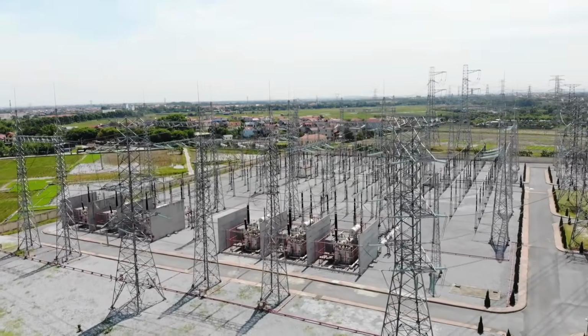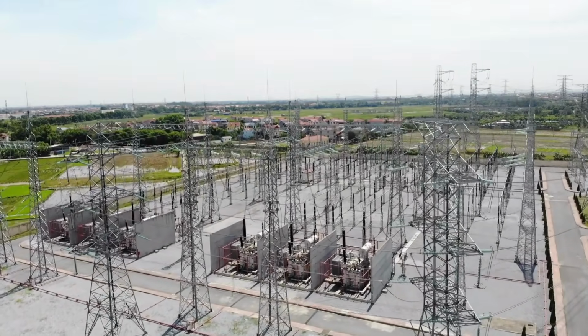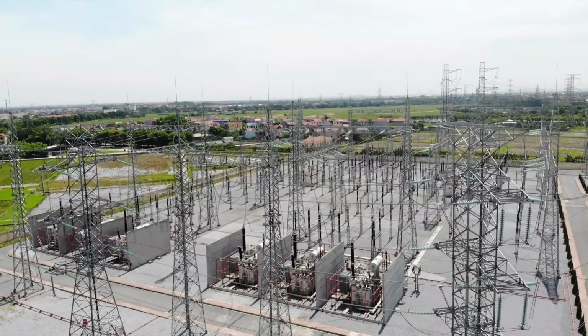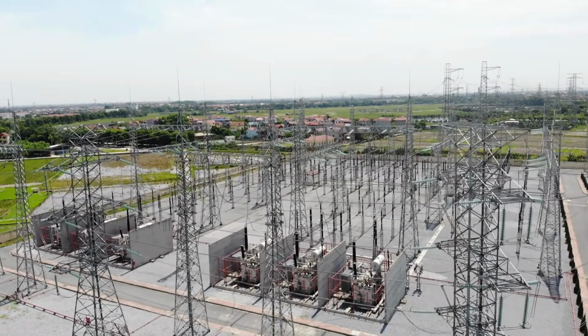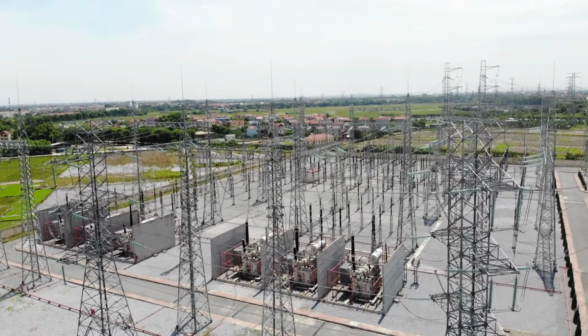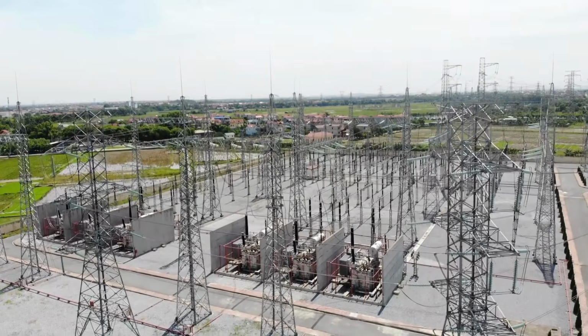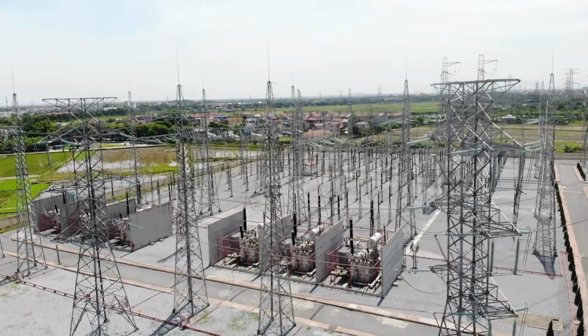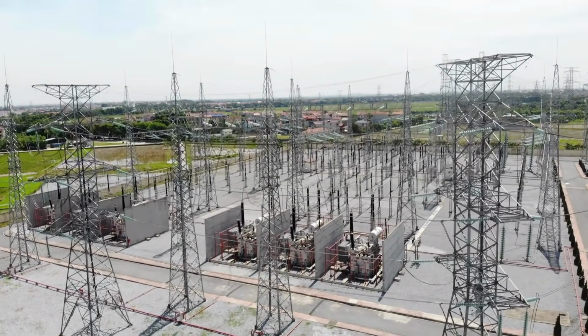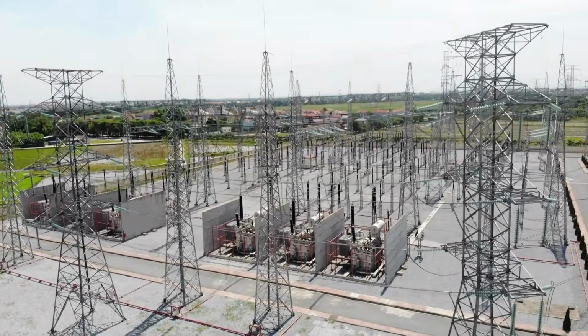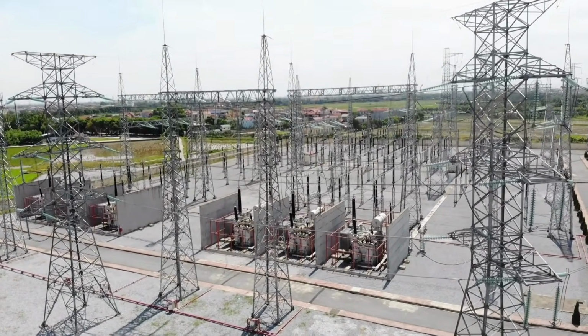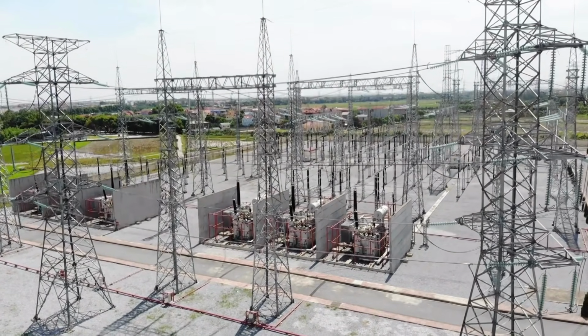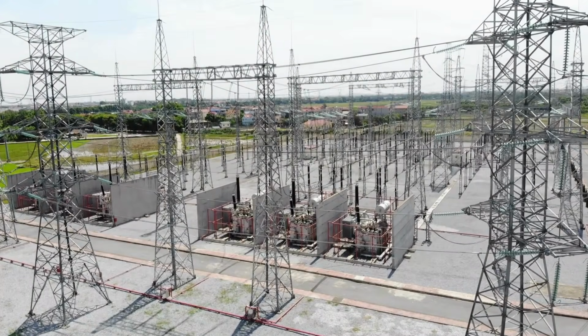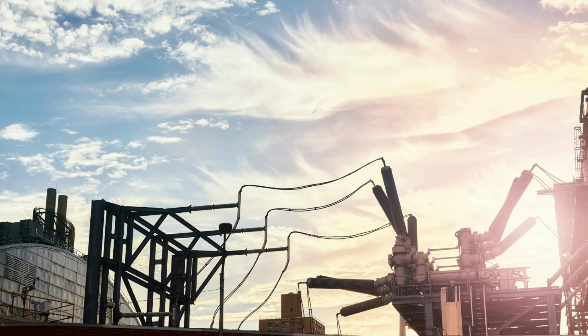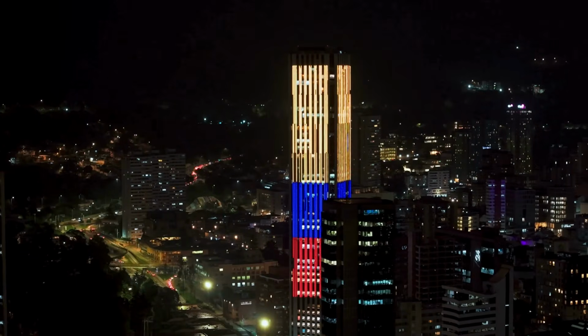Now the electricity travels hundreds or thousands of kilometers as direct current. Because DC has no frequency, no reactive power, and lower transmission losses over long distances, it becomes extremely efficient. When it finally reaches the destination, another converter station changes the electricity back into AC, and only then does it enter the normal AC grid. To homes, factories, and businesses, nothing looks different—they still receive ordinary AC electricity.